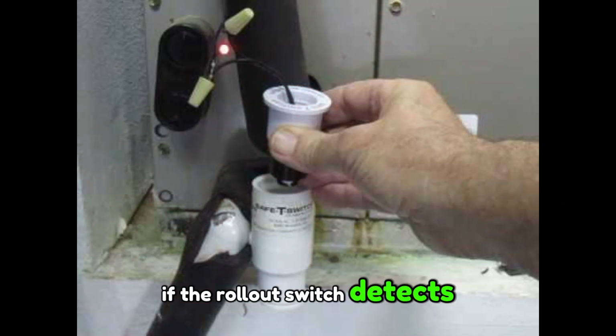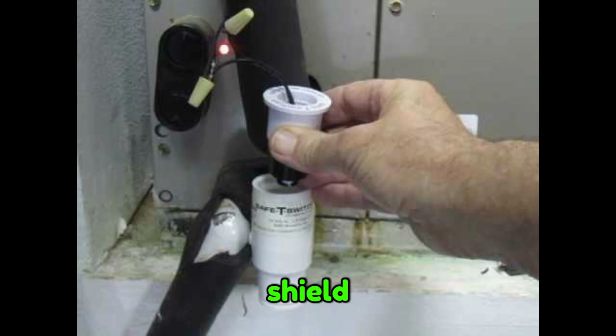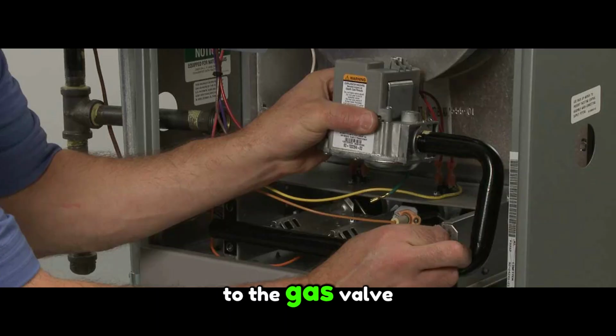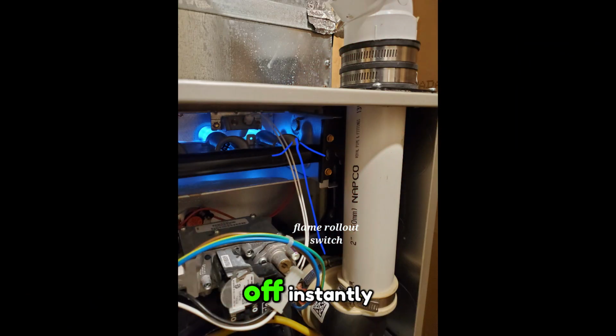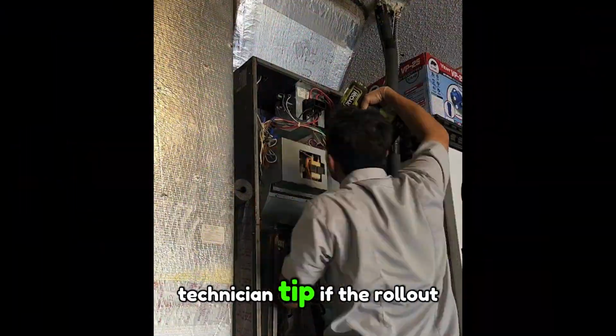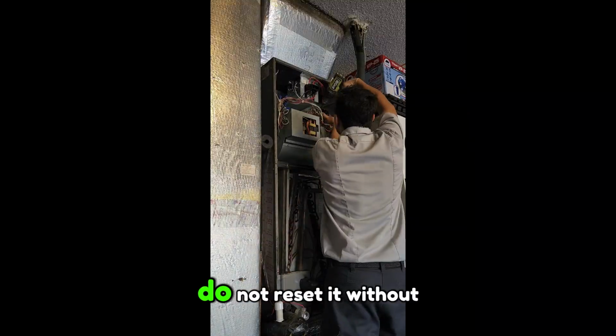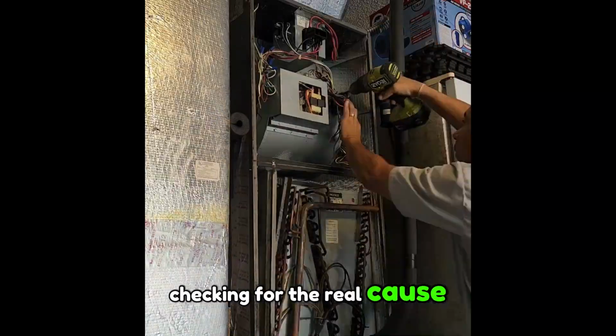If the rollout switch detects high temperatures near the burner shield, it will cut power immediately to the gas valve. You'll see the burners shut off instantly. Technician tip: if the rollout switch has tripped, do not reset it without checking for the real cause.